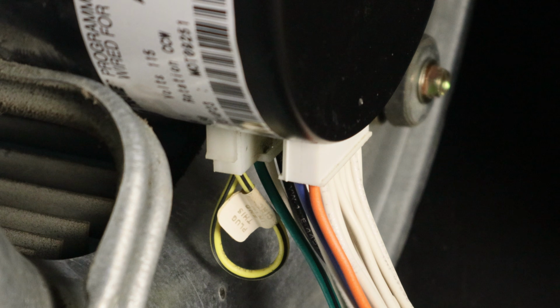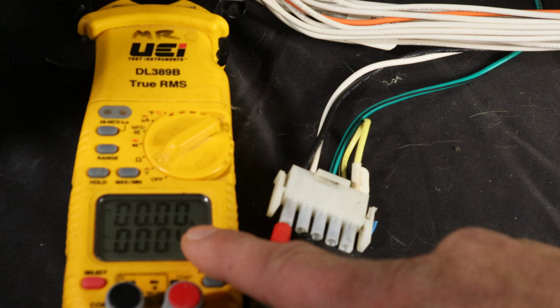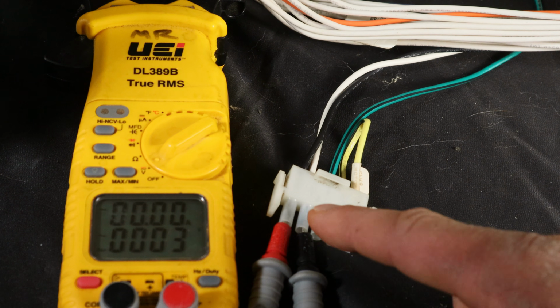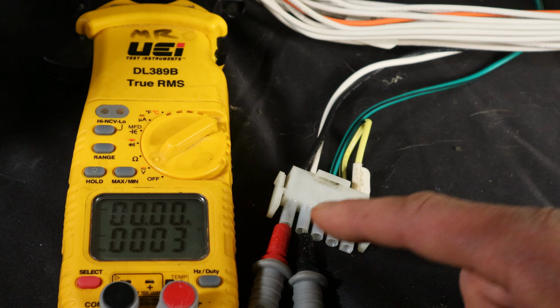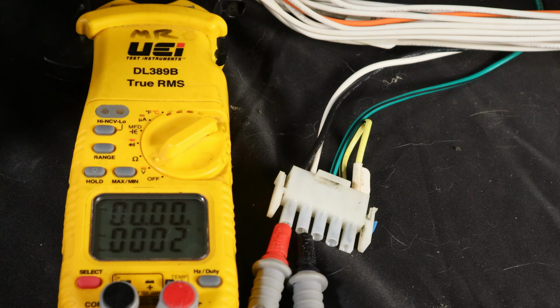Next thing I'm going to do is shut the power off. I'm going to disconnect that 5-pin Molex that the 120 volts is going to. Now, I always shut the power off whenever I'm connecting or disconnecting these Molex plugs, especially when I'm working around pretty sensitive electronics like we are here. Shut the power off, and we will pull this plug out. So once I've got my plug pulled out, I'm going to make sure I'm in alternating current voltage, and I'm going to hook up my leads to the black and the white wire. And then once I'm set up, I'm going to go ahead and turn the power back on. And as you see, I'm verifying that I do have 125 volts going to the motor. I'll then shut it back off and then reconnect the Molex plug.